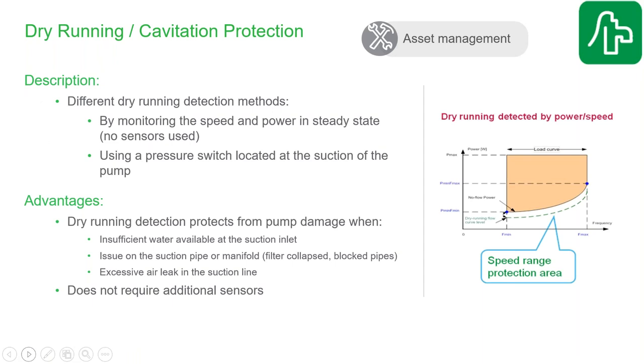So a couple of examples of this is, for example, dry running or cavitation protection. If you have insufficient water coming into the inlet, the pump is not only not going to be able to deliver the correct output, but you have the potential of it damaging the pump, either through cavitation, causing principally impeller damage and faster wear and efficiency drops in the pump, or, if there's even less water available, potentially causing overheating and damage to the pump itself.